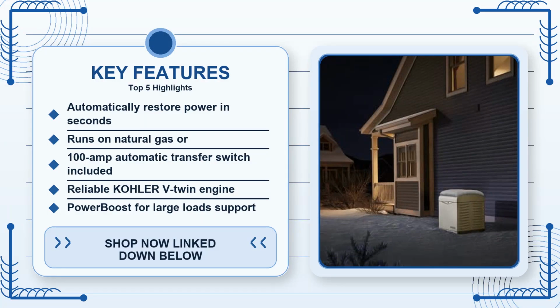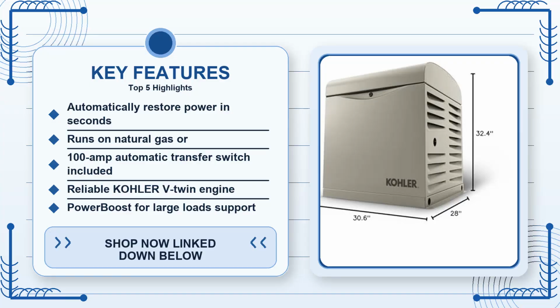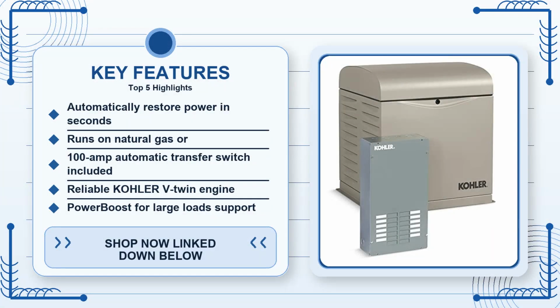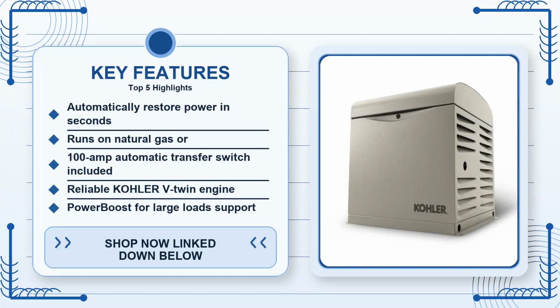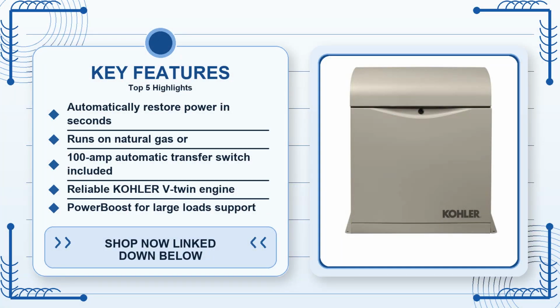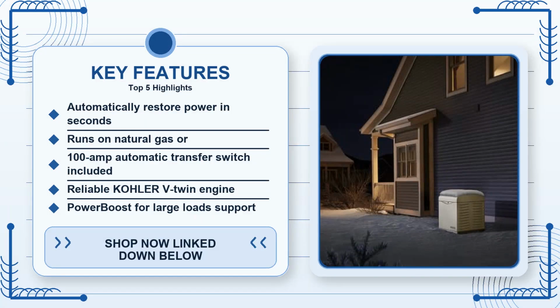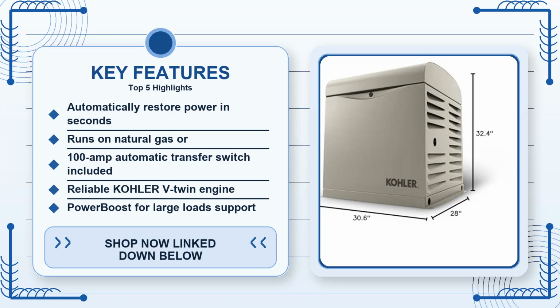The included RXT 100 amp indoor rated automatic transfer switch, ATS, has 12 load spaces. In plain language, you can assign separate circuits for the refrigerator, HVAC, well pump, garage door opener, and even a dedicated line for a home office router. The ability to segment loads means you won't be stuck with a blanket everything on or nothing on situation. In one real-world setup I observed, the homeowner programmed the ATS so the well pump and refrigerator had priority, while the air conditioner only kicked in if there was excess capacity. That kind of granularity is what turns a generator from a backup into a power management tool.